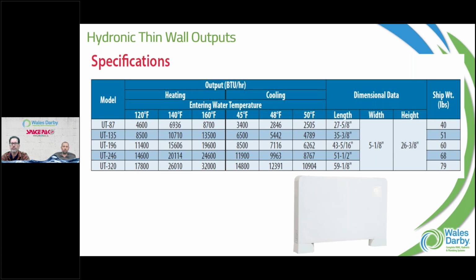But you look at load calcs, and getting into high efficiency equipment like we represent, understanding load calculations and making sure we're following them, you get an understanding of what rooms really need, and a bigger understanding of how many rooms we oversize. So taking maybe a high temp application, and if it's capable, now introduce an air to water option at lowered water temps - you could be increasing the comfort in the home just by lowering the water temp, which sounds crazy, but comfort's not always cold. We could be discomfortable being really hot or really cold.